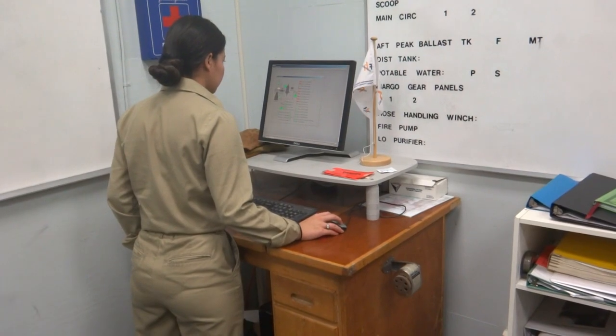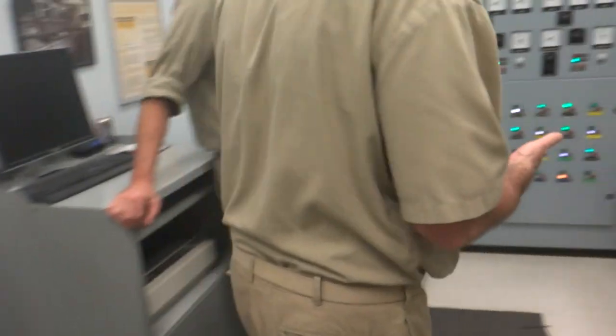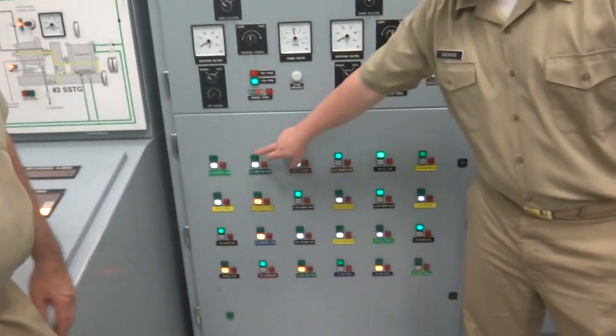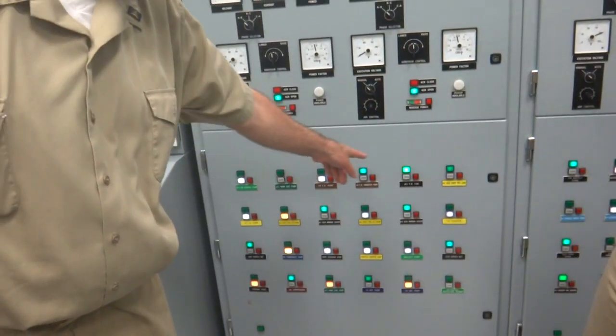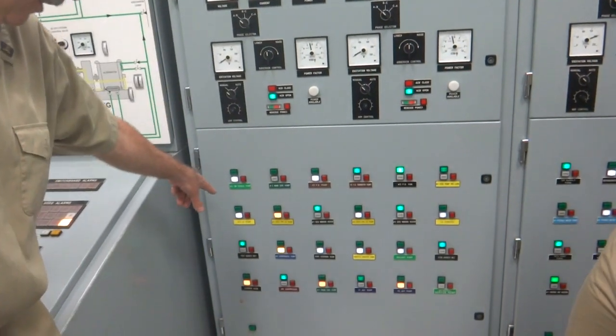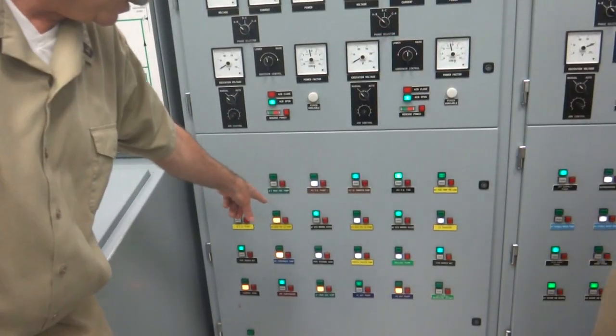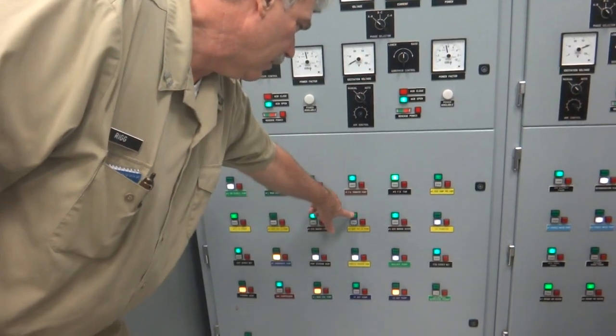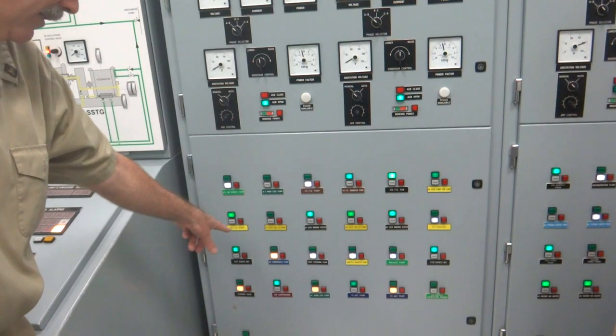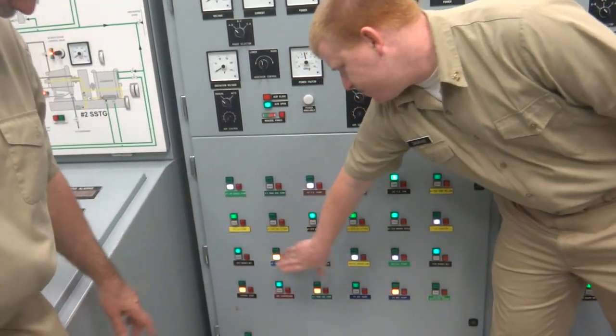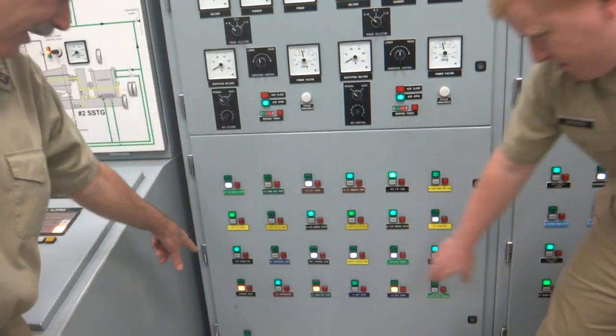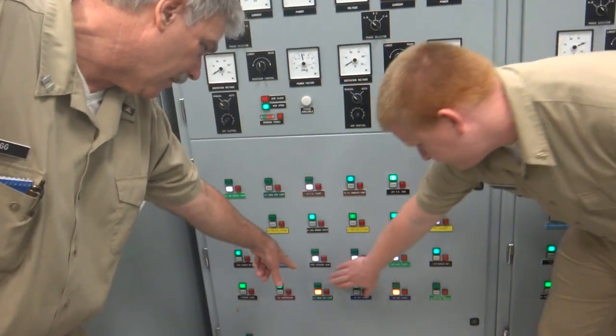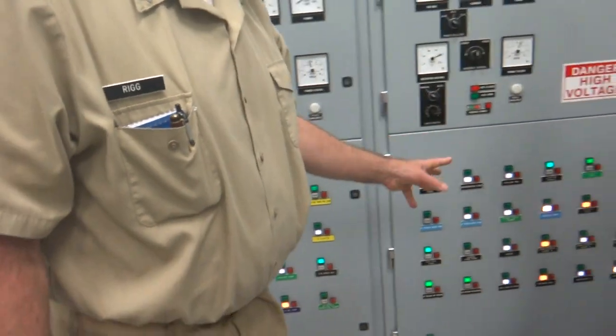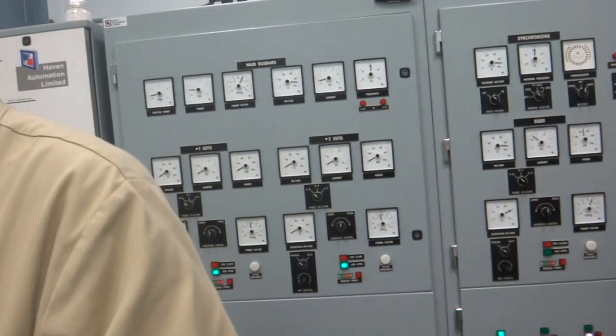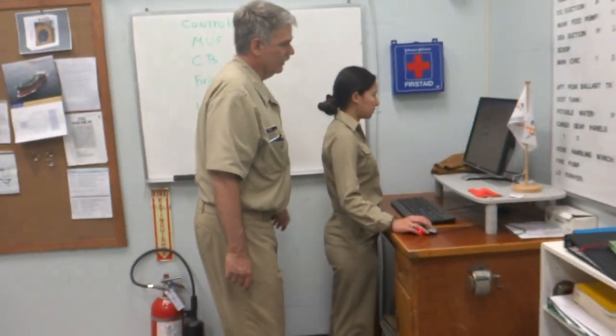Then, while she's getting control air, what do we need on the circuit breakers? We come over here. That's it. Main circ. Yeah, that'd be fine. And then what do we need? Lube oil pump number 2. That's good. Condensate. You can go ahead and get the pre-lubes. And number 2 condensate pump. Okay, turning gear. We need turning gear. Number 1 circ pump. And I think on number 2 there's nothing, but there is a lube oil pump on the emergency switchboard. Yes, please.